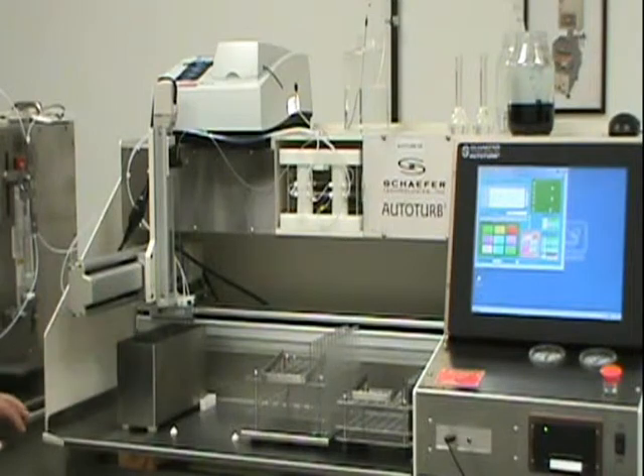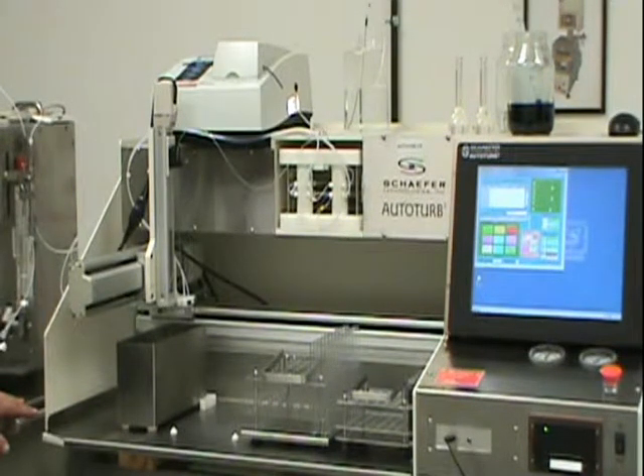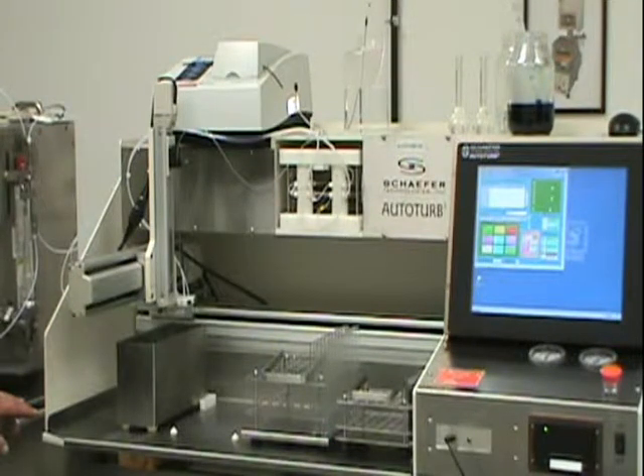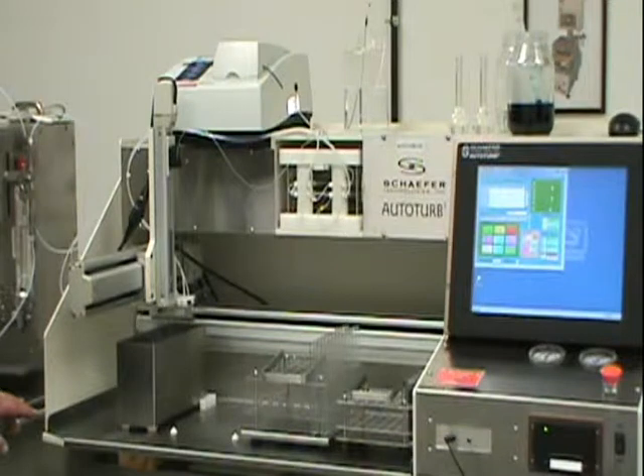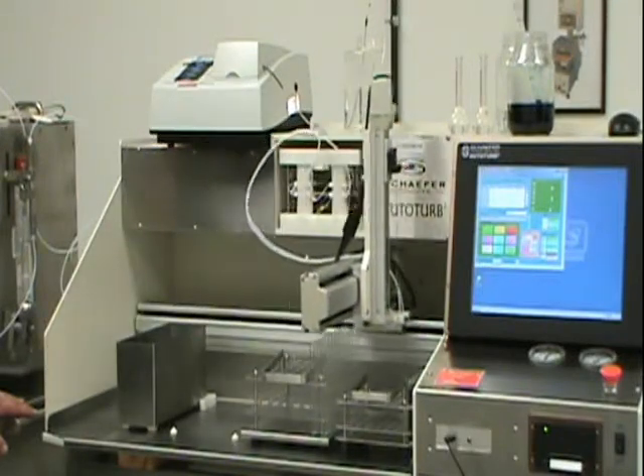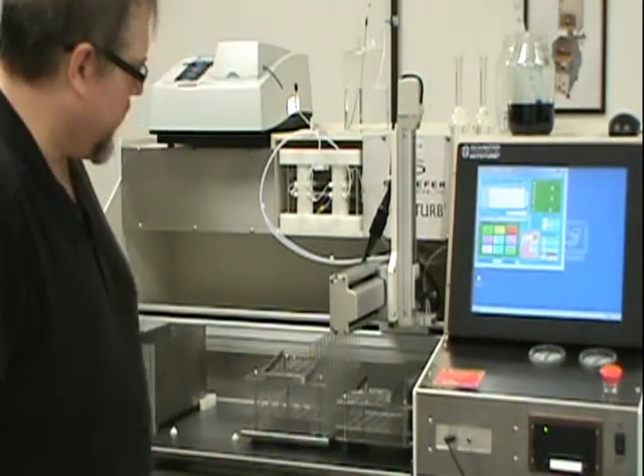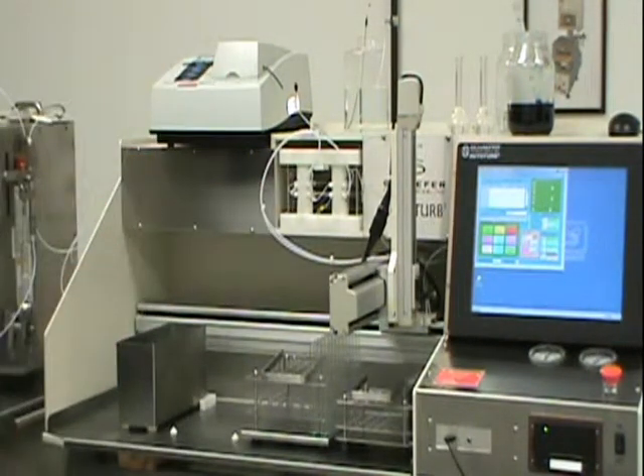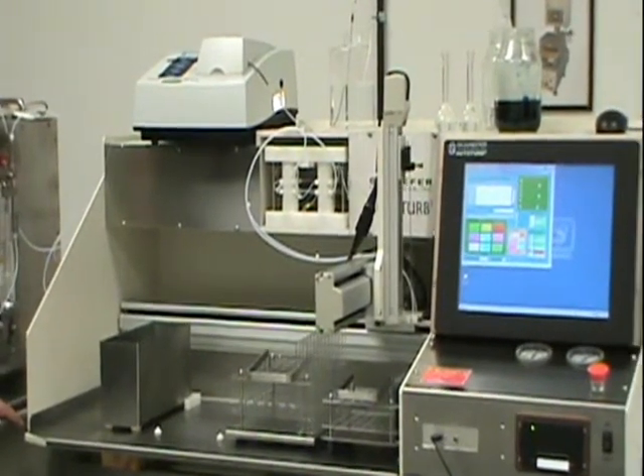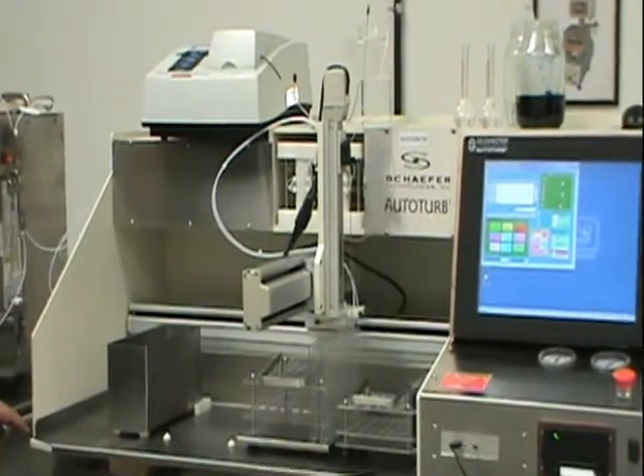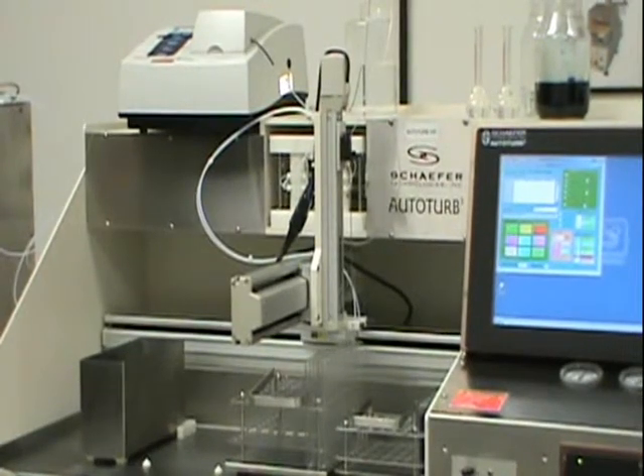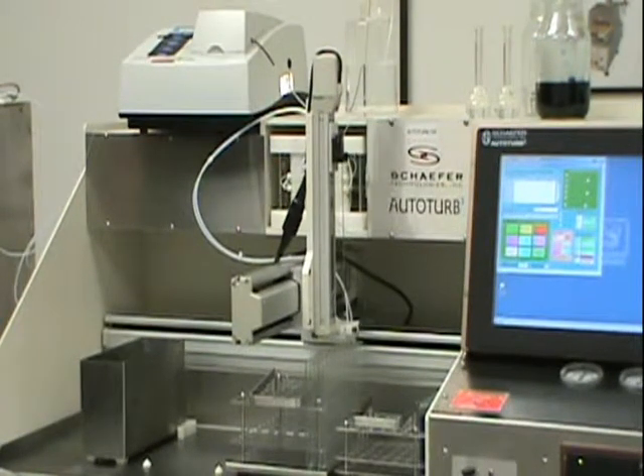The first thing it'll do is cycle twice into this pump, into the waste pan, just to make sure that everything's functioning properly one more time. Over to position 1 in the sample rack, the small rack, and it'll draw and fill these loops. In this case, we're using water, so we won't see any activity going on. The cycle is to fill both loops. Now we'll come over and dispense. The first 2 deliveries are the small loops, the 0.1 milliliter loops. We mark them 1 and 3 on the machine. And then 2 and 4 are the long loops, which are 0.15.